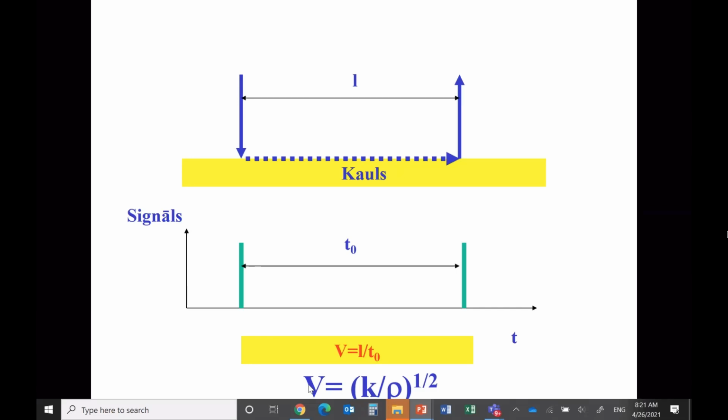So if we have a shift or changes of the velocity, this means that we have a change of the bone density. So this is an indirect measurement through the velocity to the density of the bone. And by this way, you can identify what the density of the bone is. Is the idea clear? Please, questions?